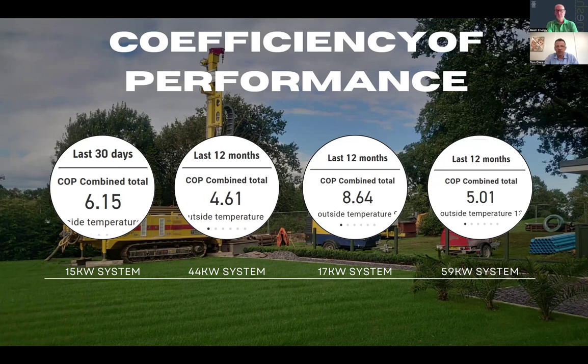But of course, the efficiency drops when the heat pump is generating hot water, because you are heating the hot water cylinder to a slightly higher temperature. So you have to boost the temperature coming from the boreholes to 50, 52 degrees. But when you are heating the house, normally the systems with heat pumps are weather compensated. So you are measuring what's going on outside on a regular basis, and the heat pump has a programmed heat curve, which then adjusts the flow temperature going into your heating system.